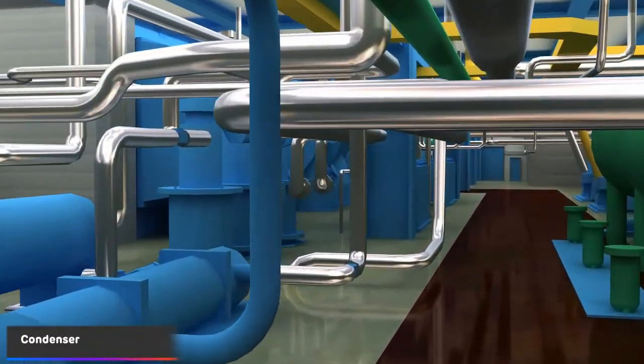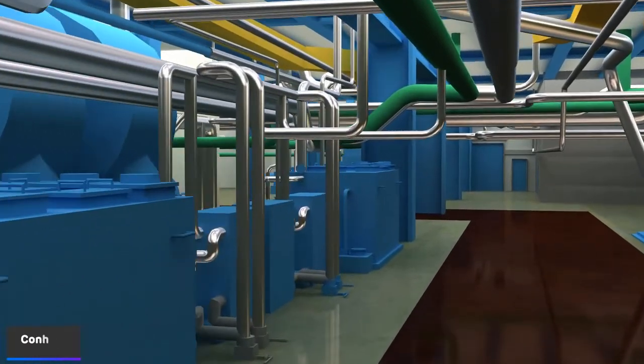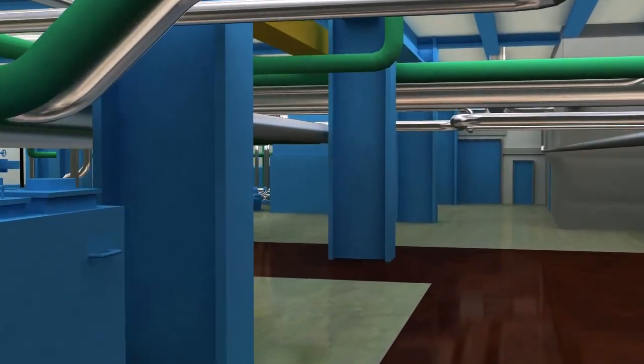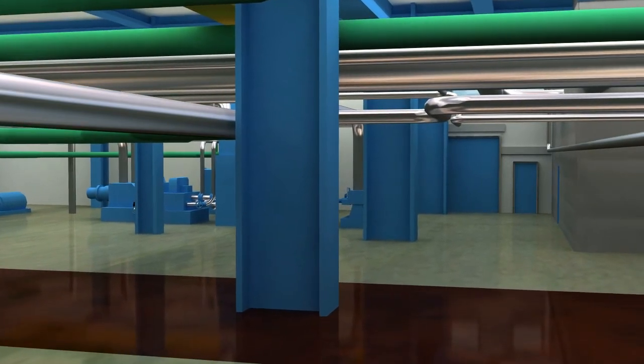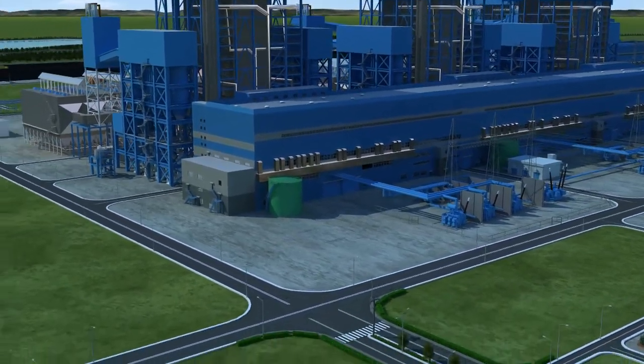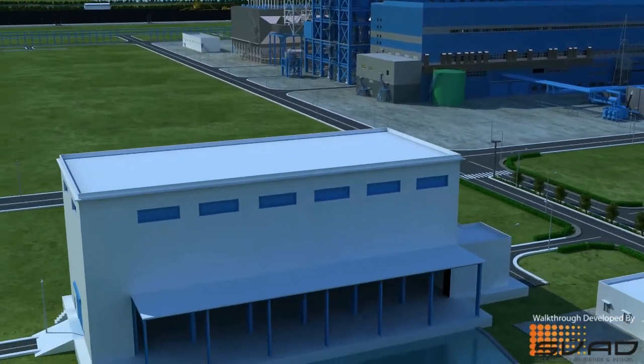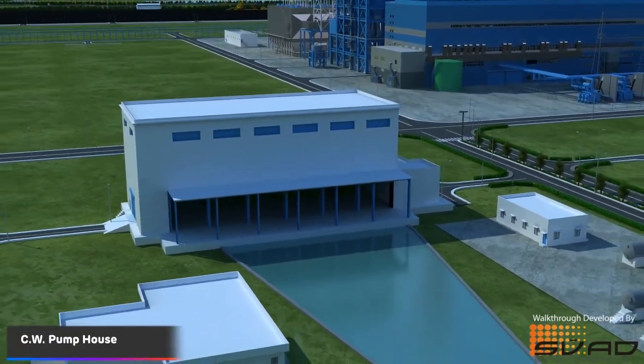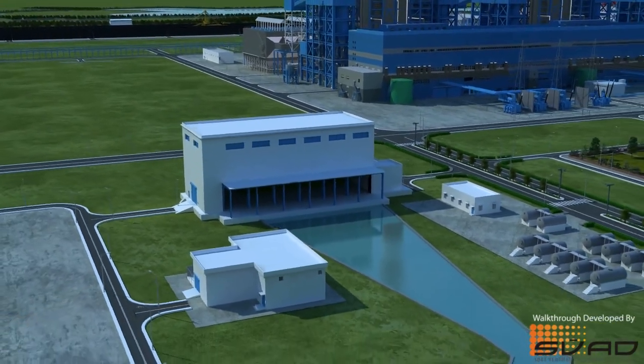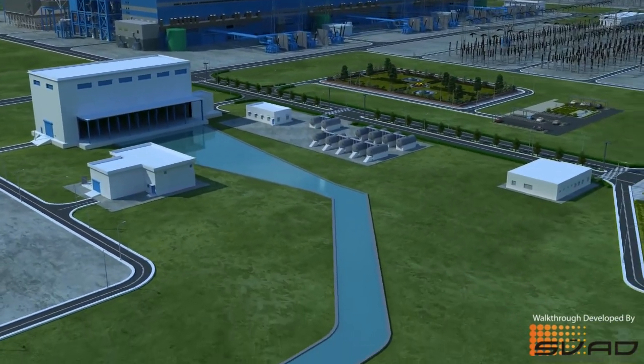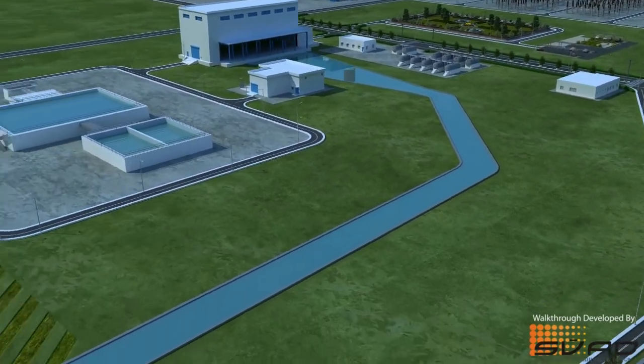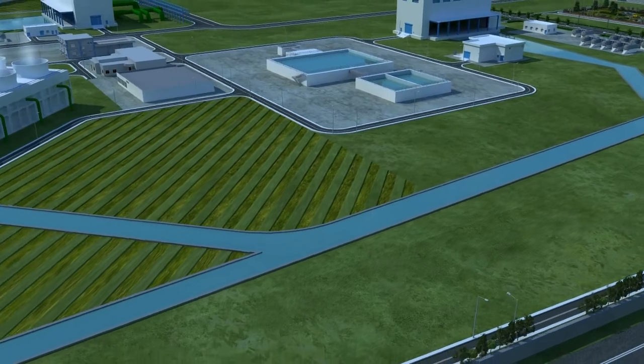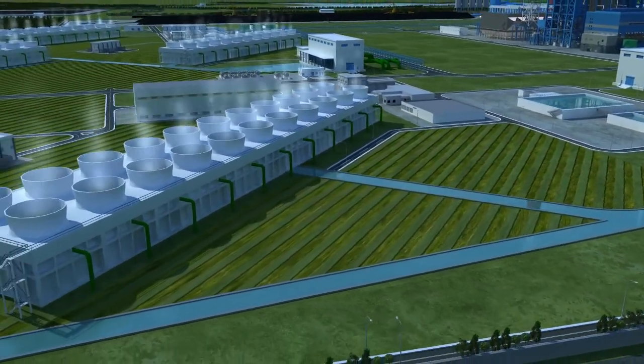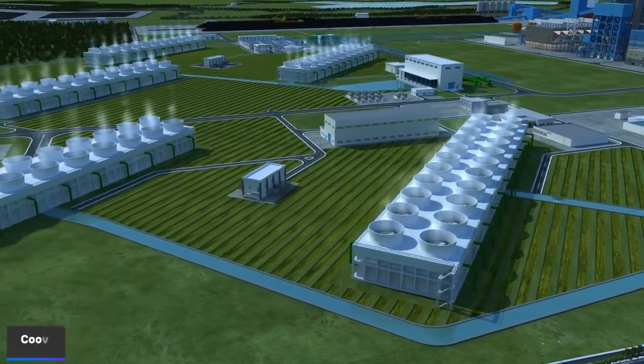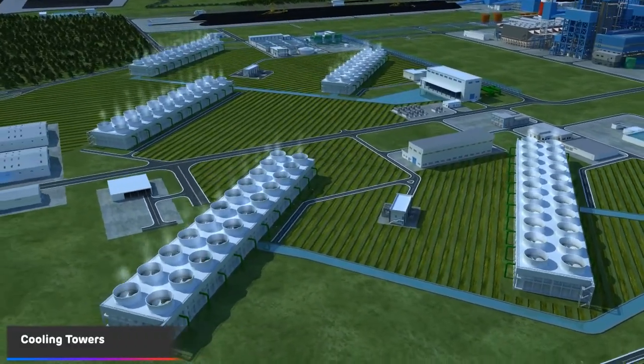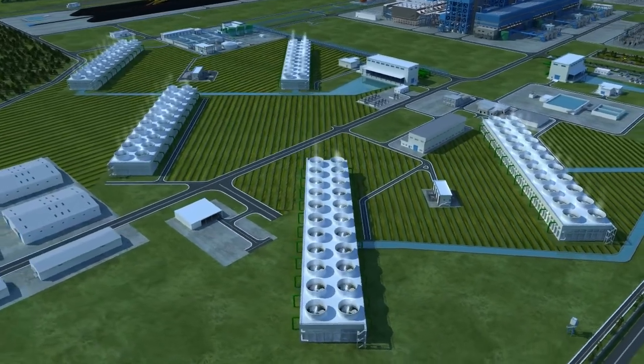Cooling of steam in the condenser is achieved by indirect cooling using river water drawn from Wainganga River, located about 10 kilometers north of the plant area. This is called the circulating water or the cooling water system. It comprises of large size circulating water pumps, set of pipelines and induced draft cooling towers. Each unit has its own cooling tower. The cooling towers have been supplied by Messrs. Bahadur Cooling Towers Limited, and the cooling water pumps are supplied by Messrs. Kirloskar Brothers Limited.